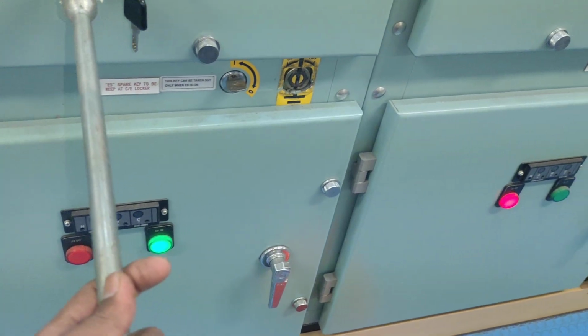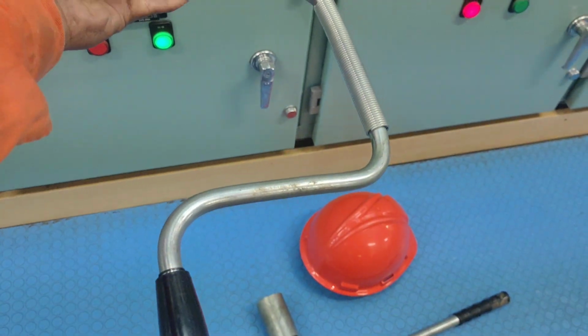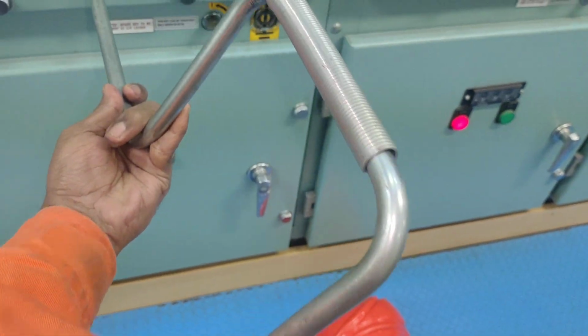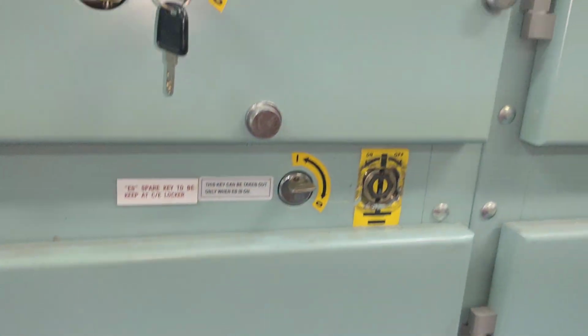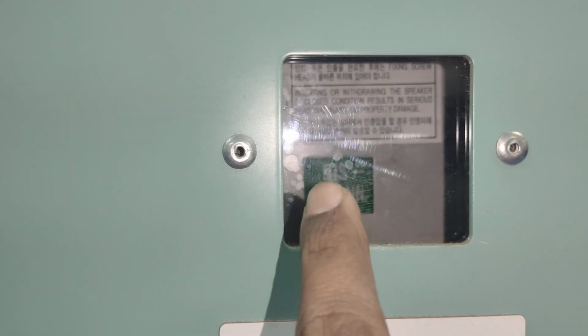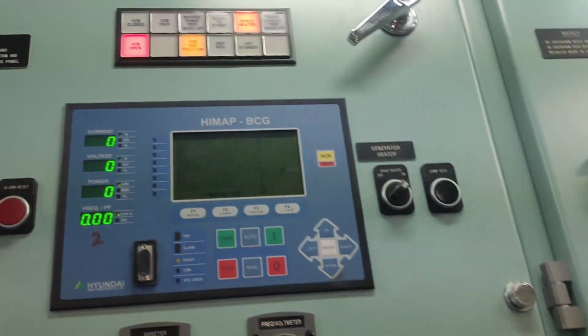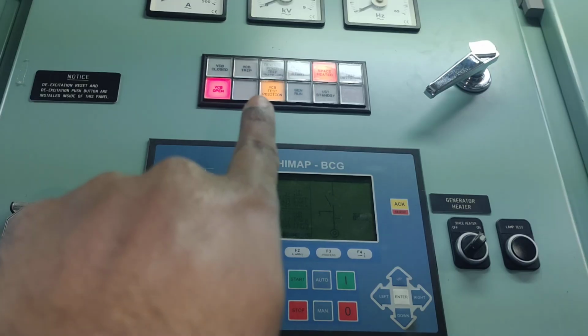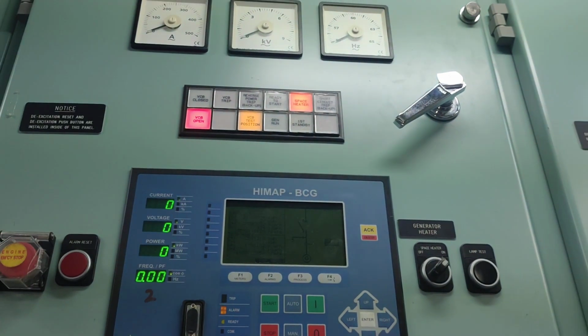Put this handle on and rotate it in the anti-clockwise direction until you see the breaker is disconnected. The breaker is disconnected, and the VCB is now in the test position.